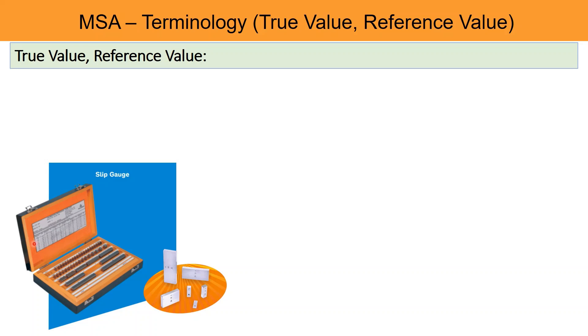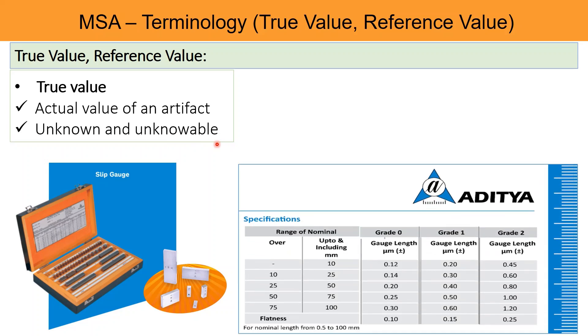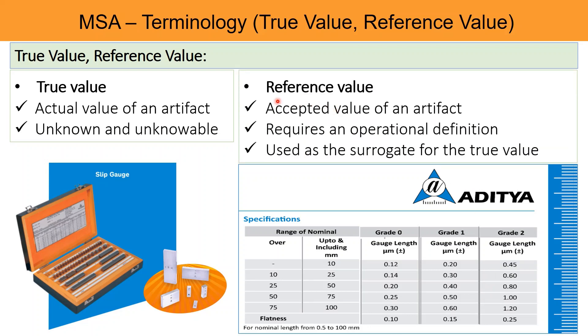True Value is the actual value of an artifact or a part. It is unknown and unknowable. In the specification table for a slip gauges set, the nominal value and tolerance range are tabulated. Within the tolerance range, the true value may lie anywhere, but it is unknown. Reference Value is the accepted value of an artifact and requires an operational definition. It is used as the surrogate for the true value. Since the true value is not known, the value taken into consideration is called the reference value.